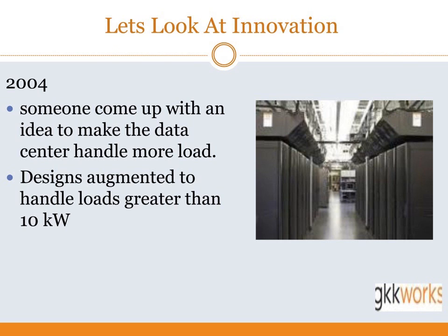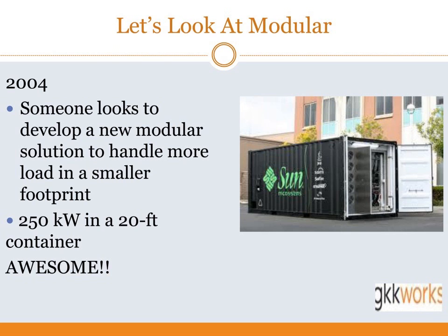But that was a temporary band-aid, a means by which to gain ability to handle more heat. Now that heat has started to increase. We're seeing data centers operating at anywhere from 10 to 25 kW at the rack level, and it's not becoming just concentrated in distinct areas, it's spreading and continuing to proliferate in the data center environment.